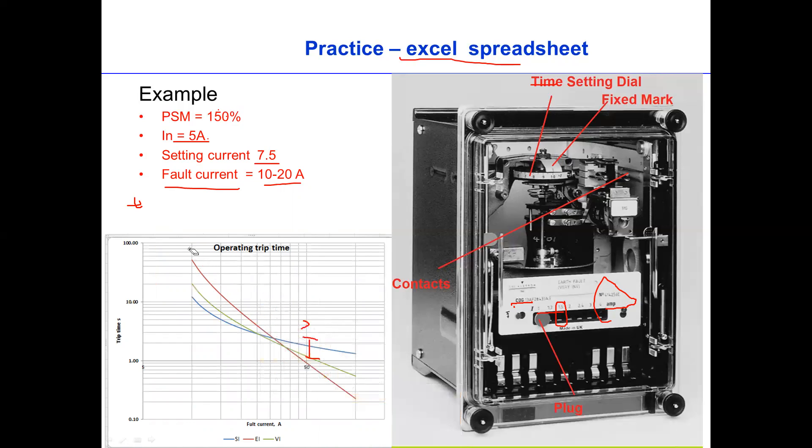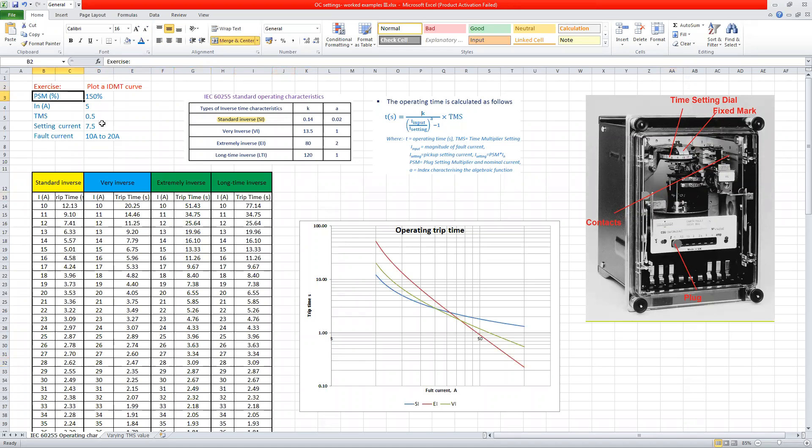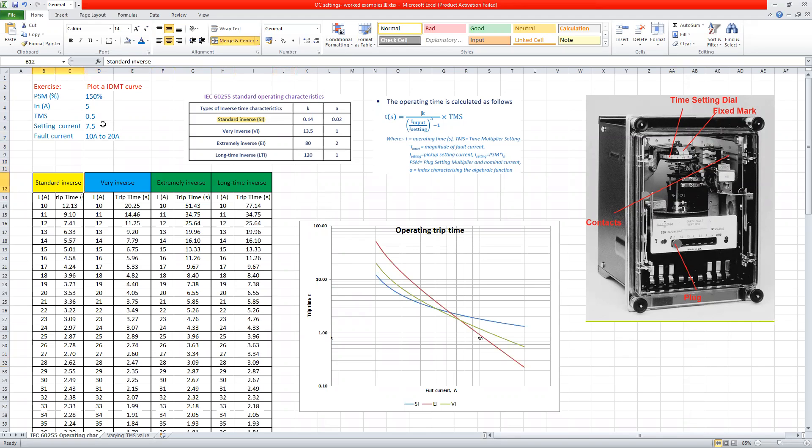We should expect something like this, but for different kind of types. For example, for a standard inverse, we should have this way, and extremely inverse this way, and very inverse this way. So let's have a look at the Excel spreadsheet. As you can see, we have this one in Excel. So the time multiplier is 0.5 and nominal current 5. So the setting current is 7.5, and then the current is 10 to 20. So if we pick the standard curve, for example, this is the standard curve.